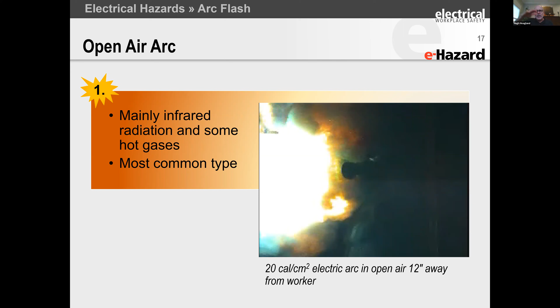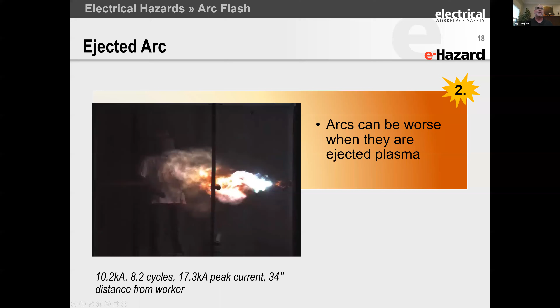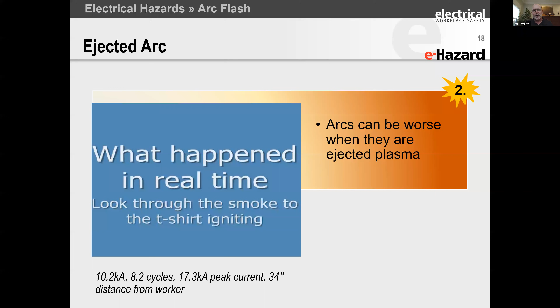But arcs can be totally different than that test. That test is designed to be very repeatable. Arcs like this, we call this an ejected arc. And this is one of the papers I did in IEEE many years ago. This is where the plasma is actually shooting out toward the worker. This is a really rare occurrence in real life, but it does happen when you see a stab pointing out like a switchgear. If the stab is pointing out rather than pointing down, the arc is going to come straight out toward you.